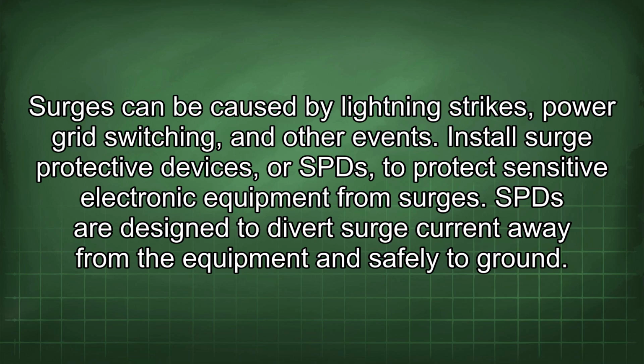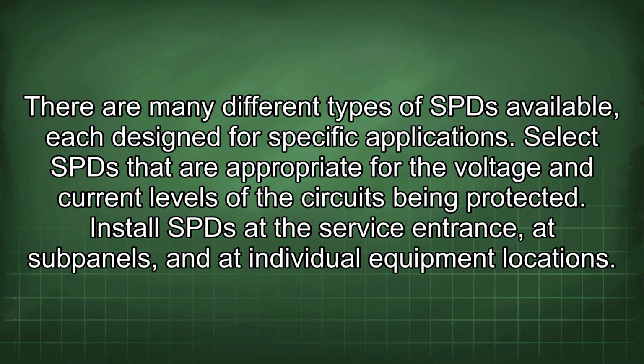Install surge protective devices, or SPDs, to protect sensitive electronic equipment from surges. SPDs are designed to divert surge current away from the equipment and safely to ground. There are many different types of SPDs available, each designed for specific applications. Select SPDs that are appropriate for the voltage and current levels of the circuits being protected. Install SPDs at the service entrance, at subpanels, and at individual equipment locations.